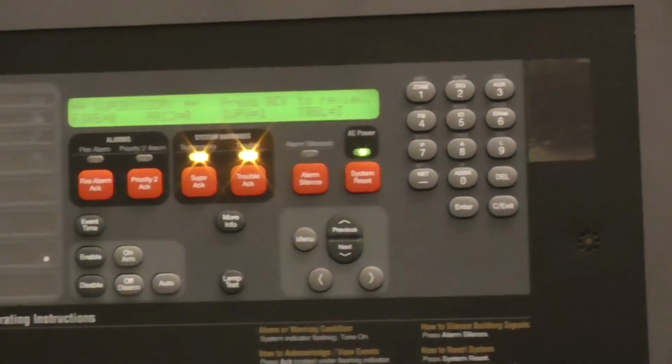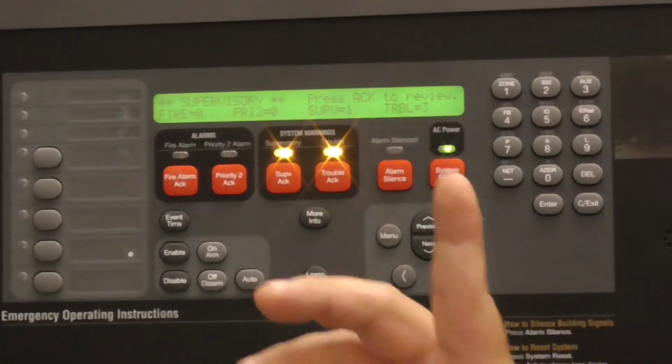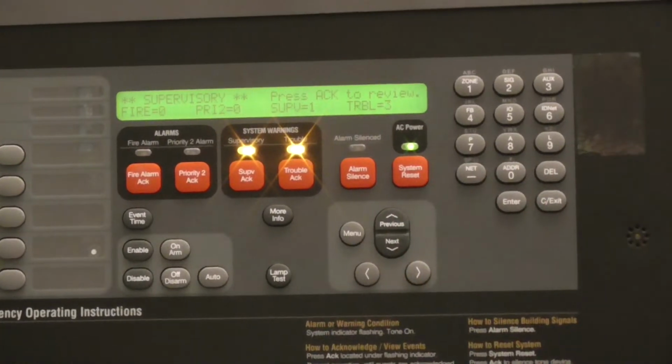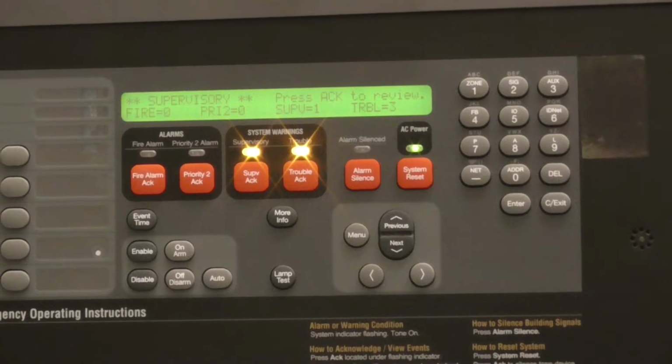Same thing for a smoke detector. If it's still under detection, if it sees anything above about 2.5% smoke, it'll stay in alarm and keep aborting your reset. That's the same thing with the latching supervisory. It's still seeing smoke, so it's saying, hey, I'm not resetting until it's clear.